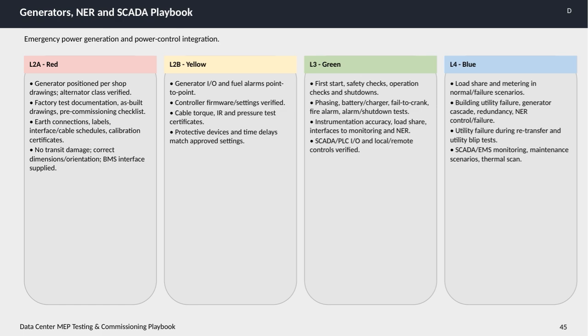Additionally, the generator must be free from any transit damage, with the correct dimensions and orientation, and have the building management system interface applied as specified. Moving to level 2B, indicated in yellow, this stage covers detailed point-to-point verification of generator I/O and fuel alarm points. We verify the controller firmware and settings, check cable torque, insulation resistance, and pressure test certificates. Protective devices and time delays must match the approved settings to ensure reliable operation.